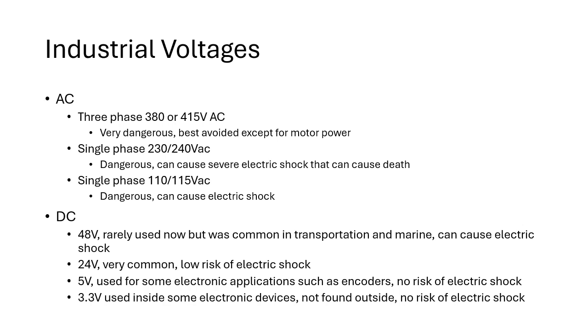The problem is, as the voltage goes down, the susceptibility to external noise can cause EMC effects, which can cause noise and interference. So even down at 5 volts, that's an issue. Simple noise can easily affect a 5-volt encoder. So modern encoders are normally 24 volts. And when you're getting down to 3.3 volts, that's a much lower voltage. So on the plus side, no risk of electric shock, but it could potentially not be noise immune. And again, for large currents, you've got that additional conductor size you'd need.